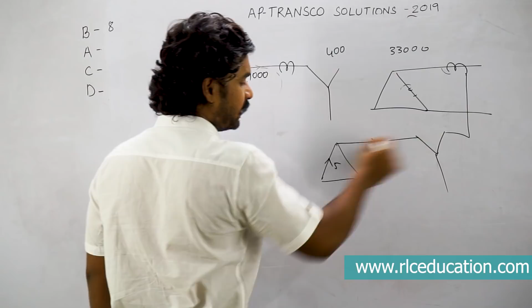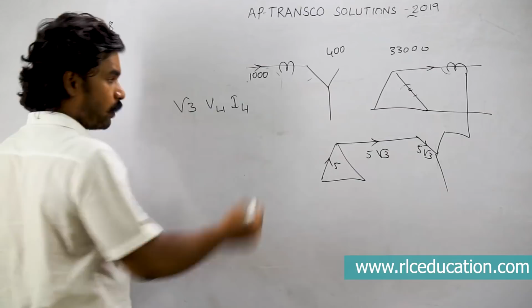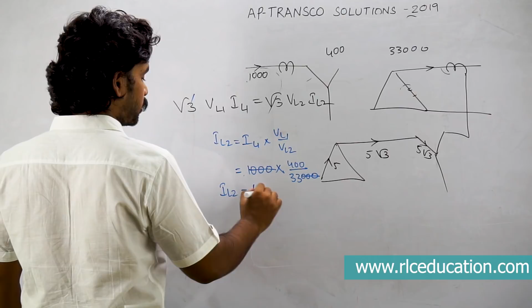Understood? So if 1000 is flowing in the line of the primary side, I want to find out how much current will be flowing in the line of the secondary side. I can find that directly by this relation: root 3 VL1 IL1, which is the volt-amperes on the primary side, will be equal to root 3 VL2 into IL2, as simple as that. So root 3 cancels out, and from this I can write I line 2 will be equal to I line 1 into V line 1 by V line 2. So what is I line 1? Line current on the primary side is 1000 and V line 1 is 400 divided by V line 2, which is 33,000. So the 1000 cancels. You will get I line 2 as 400 by 33 amperes. So this is the line current flowing in this way.